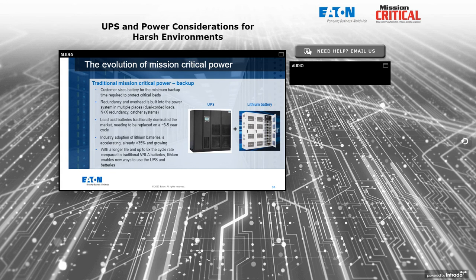That's why we see the advent of lithium batteries with UPSs, because of their usually guaranteed 10-year service life and expected service life in UPS applications approaching 15 years. That depends on temperature and depends on the number of cycles, but the primary reason we get longer longevity from lithium-ion batteries is their ability to withstand, in some cases, thousands of charge-discharge cycles, which is much more than I would find with a traditional UPS battery. So the advent of lithium batteries with UPSs opens the door to some new applications that we'll look at on the next couple of slides before we finish up here.